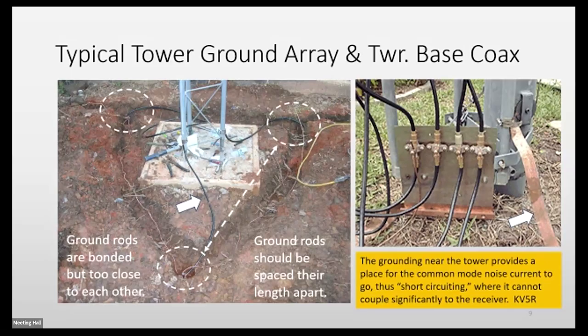For ground rods to be of full value, the spacing between them needs to equal the length of the rod, because that's how ground rods work. If you get them closer than their depth in the ground, you don't have the full capacity of the ground rod — you've lost part of it. So separate them out further, which is much more valuable. You're buying a rod you're going to pound in the ground and never see again, hopefully, but get it out a little ways away.